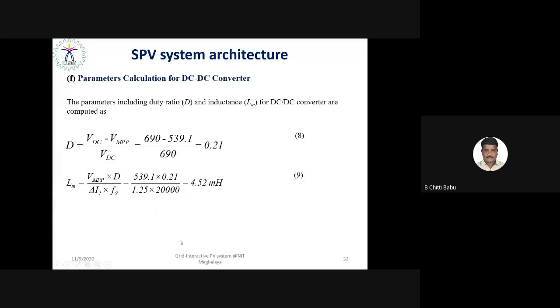And the DC to DC converter, which we use as the maximum power point tracker on the source side, is basically extracting the maximum possible power of 13.5 kilowatts from the array. It is boosting the voltage from 540 volt to 690 volt. So the boost converter is designed with a duty cycle of 0.21, and the inductance of the boost converter would be around 4.52 millihenry, assuming the current ripple is around 25%.